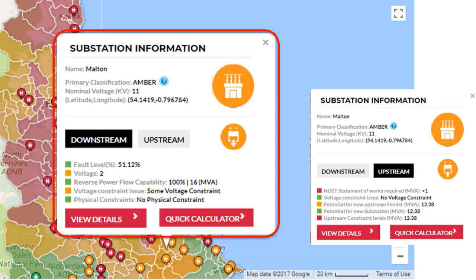When you look at the downstream button, this is trying to give you some clues about how constrained the network is looking outwards from this substation. It's a 66 to 11 kV substation, so this is looking out into the local 11 kV network, which is where smaller projects will be connecting. So it's telling us about the fault level. Some of these terms are technical and may not mean a great deal to a lay person, but if you're more technically minded, you'd appreciate that the fault level here is not particularly high. So we've given it a green marker.